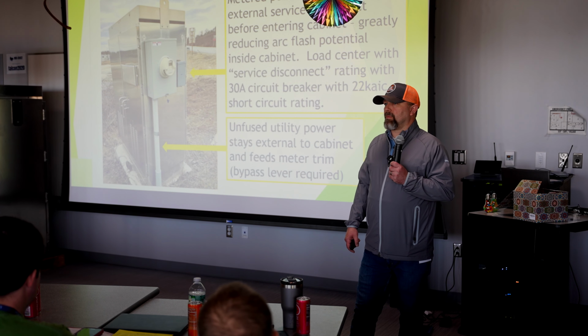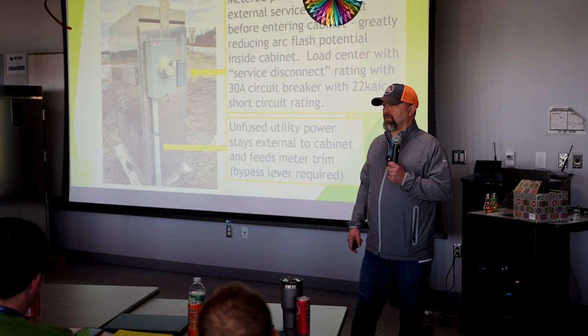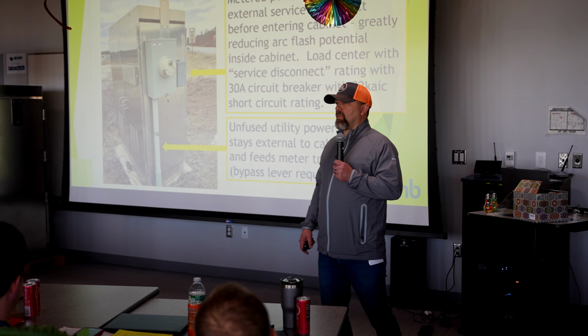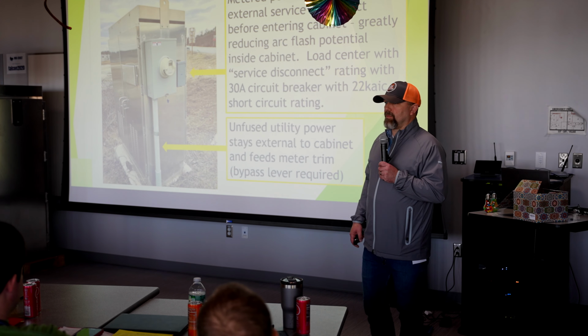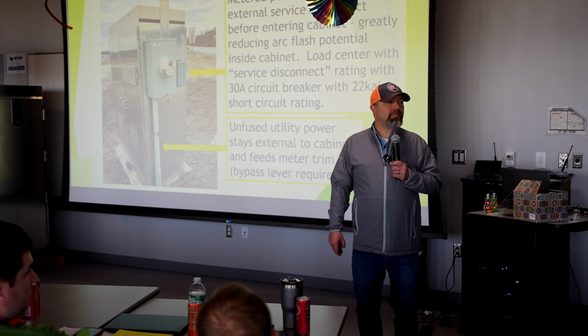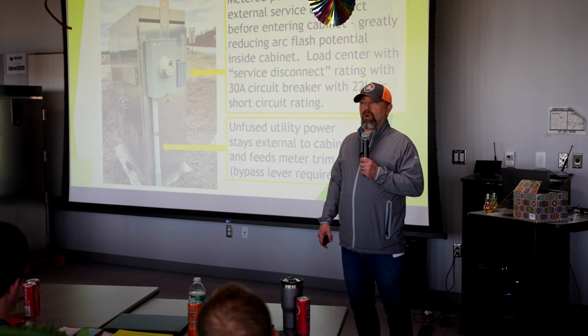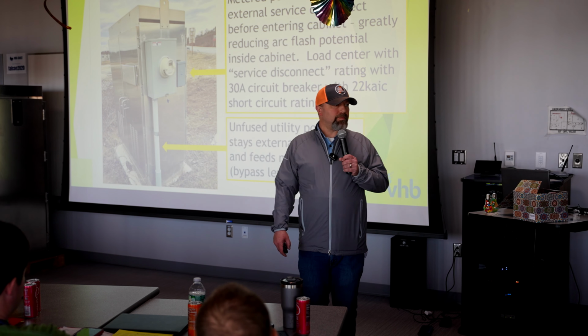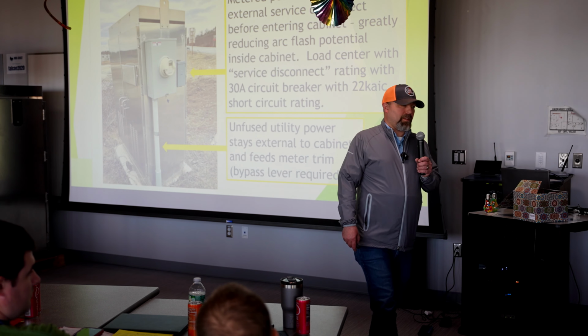But before any breaker is put in, you really should contact the power company and ask for the maximum short circuit current for the transformer, based upon the size of that and the run. Otherwise the breaker may or may not open. You have to do an arc fault calculation before you size that.